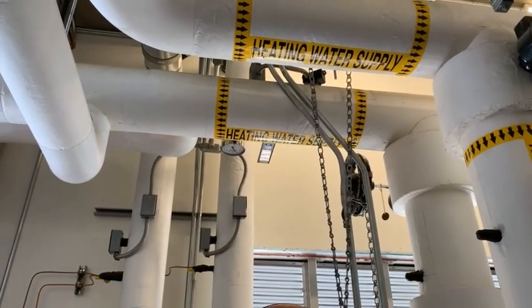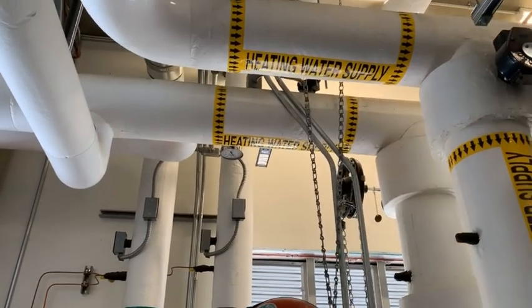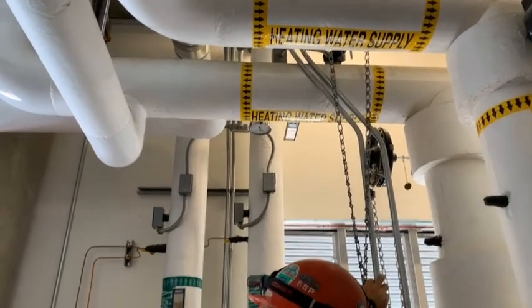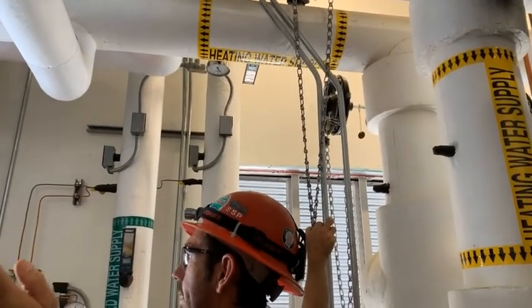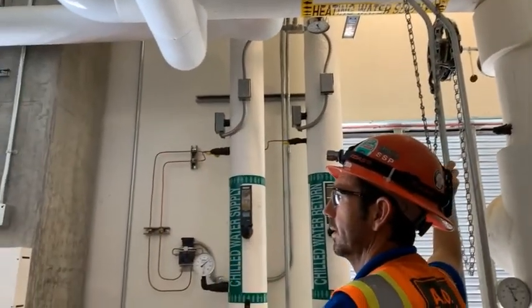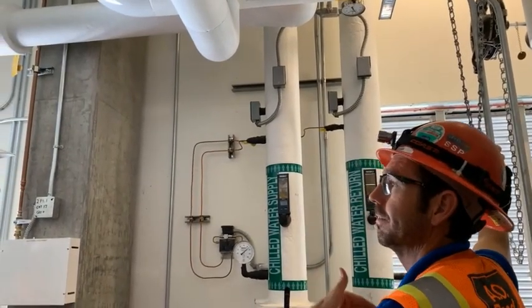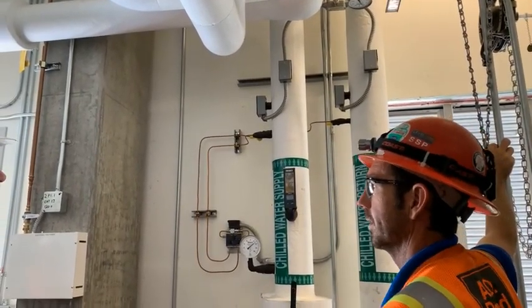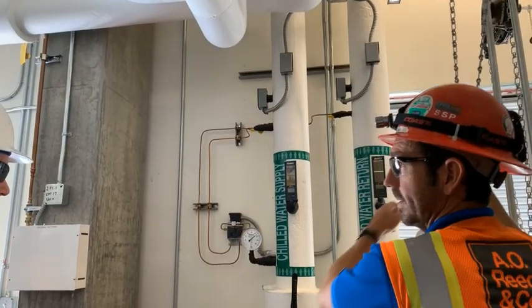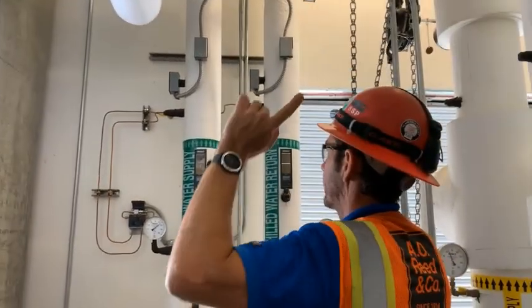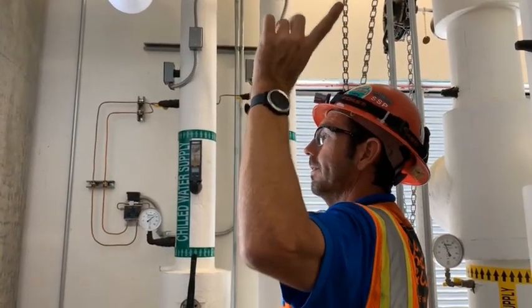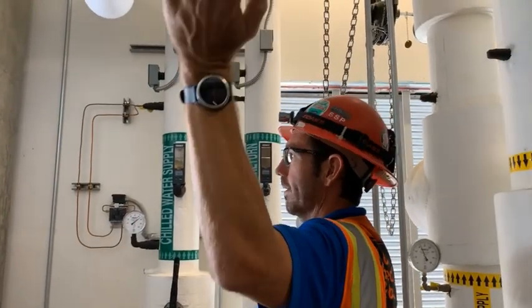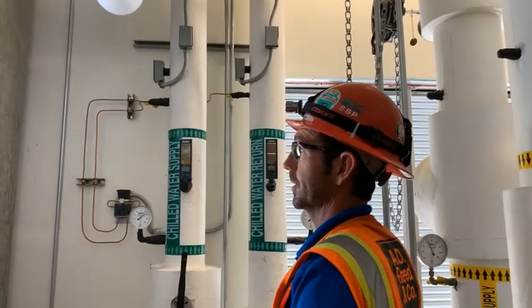It depends. Again, if you had a situation where you need to create a primary, secondary, where the 41 degrees ended up not being a good temperature, and you try to bring it up, but it was here for flushing and needs to stay closed. That's the most important thing that we know for right now. Because if this thing starts cracking open, you're probably going to start seeing like 50 degree, 55 degree water. You're going to get warmer water in the building than what you're wanting, especially if a pump is running.